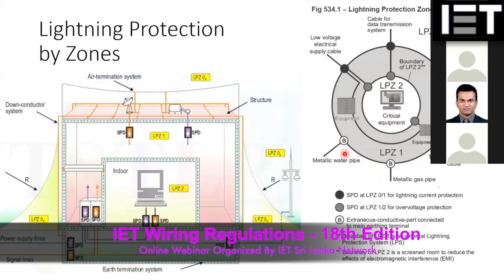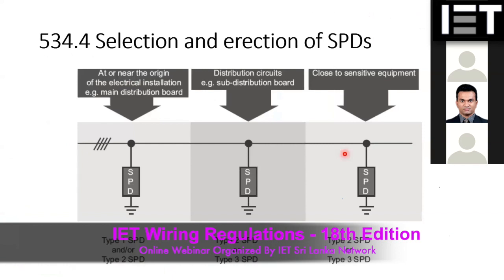BS 7671 has basically adapted the IEC 62305 standard, so that also gives us the lightning zones and the zone protection. So here also we have to follow the zone protection. We have to subdivide the electrical installation into different zones depending on the risk level, and then at each interface, let's say zone 0 to zone 1, zone 1 to zone 2, zone 2 to zone 3, we have to put the surge protective device appropriately. That is a new addition to the standard. Now, when you look at SPD selection, very comprehensive selection criteria are also given in the standard, which were not in the earlier version.